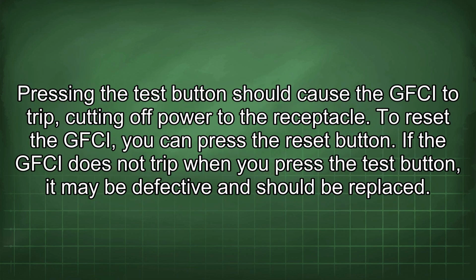Pressing the test button should cause the GFCI to trip, cutting off power to the receptacle. To reset the GFCI, you can press the reset button. If the GFCI does not trip when you press the test button, it may be defective and should be replaced.